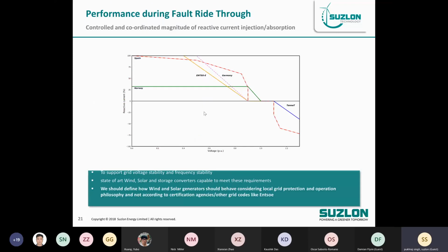Here you see what is expected during the fault. Every country has different requirements for response time and the magnitude of reactive current that has to be injected during faults. But at the park level, it's quite challenging to prove this. Sometimes grid codes say, let's wait until a real fault happens to see how your park responds, and then we'll determine compliance.